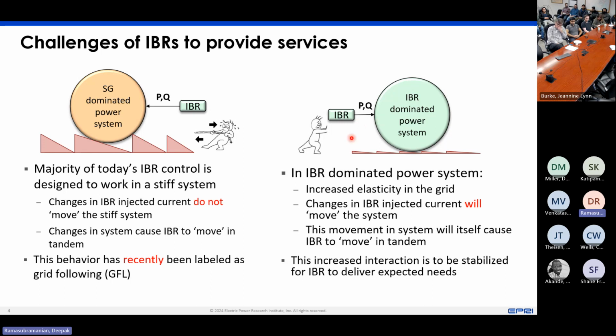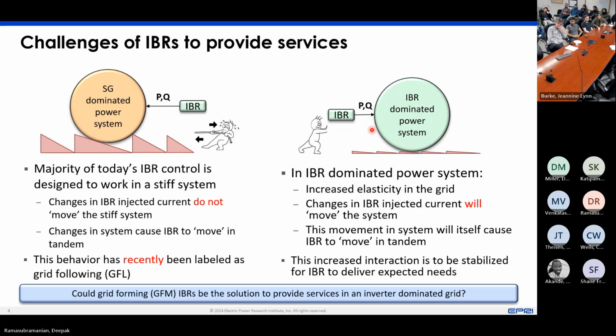That change in the electrical profile causes this to change its injection, which again causes this to change its electrical profile, and so on. So there is a cyclic loop that develops, which can become unstable. This is the challenge we see for inverter-based resources providing services: the more services we require from a resource connected to the grid, the more it can cause increased cause-and-effect loops, and those loops can have consequences we may not have prepared for.